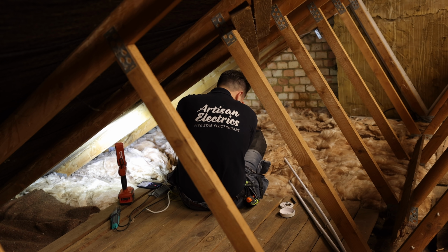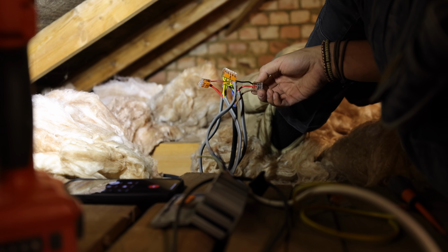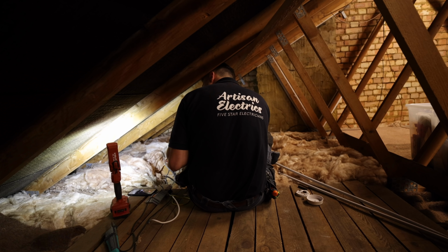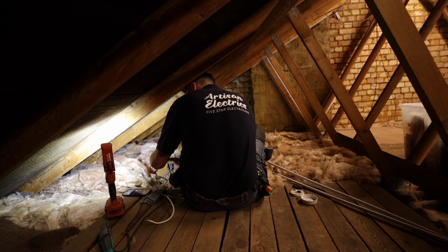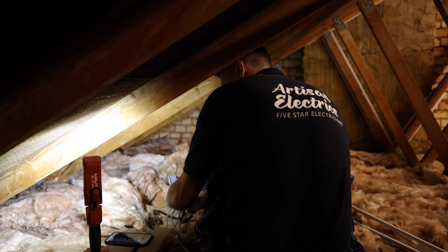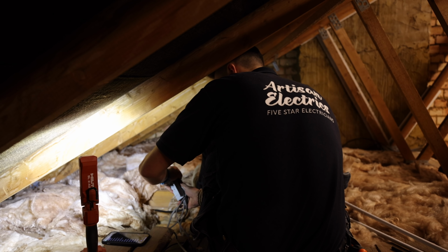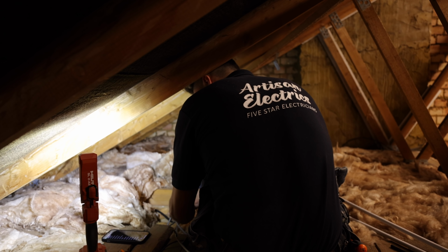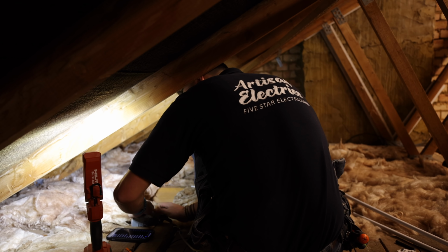Just turn my head in, this job will not end. Yeah, mine's on. Oh, no, the one furthest to you is on. So the one that's underneath me stays on regardless? No, the one that is under you, just turned off. I think you've just mixed up a switch line and a feed. Easy mistake to make. Yeah, both on. Touch them together. Both on. There you go. You mixed up a switch line and a feed. No worries. Right, let's carry on getting tidy, getting back together. In fact, you need to tidy up here, mate. All right, so that was an easy mistake to make. It's just the wiring that's in this place is very aged and not very well labelled. He's mixed up a switch line and a load, hence why it was switching between them.